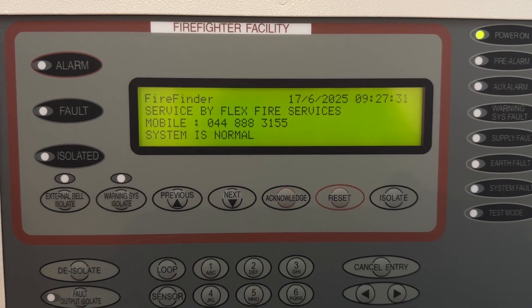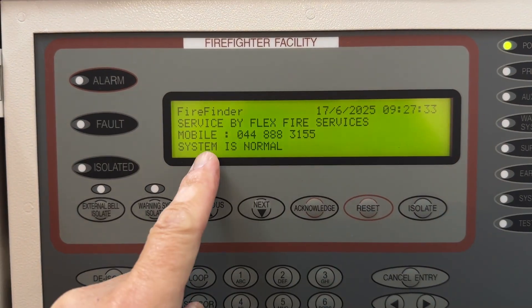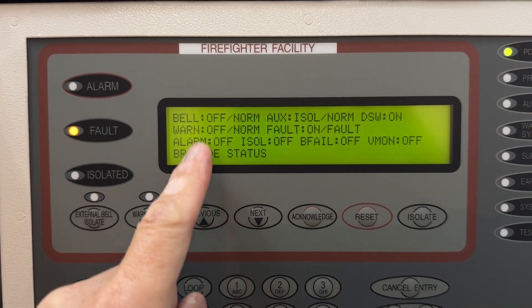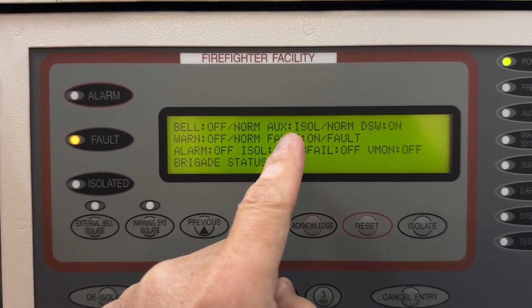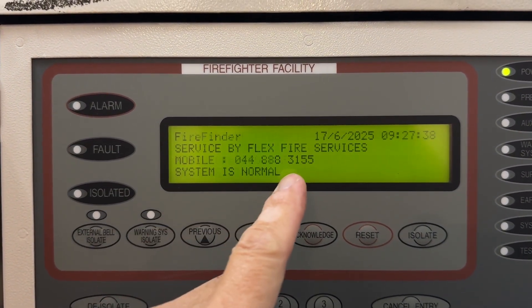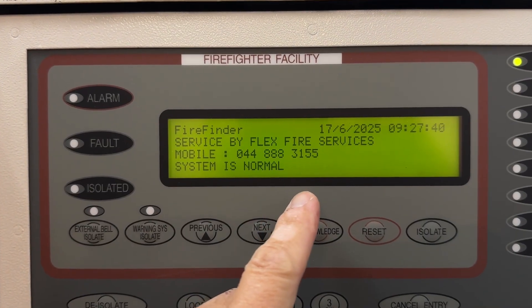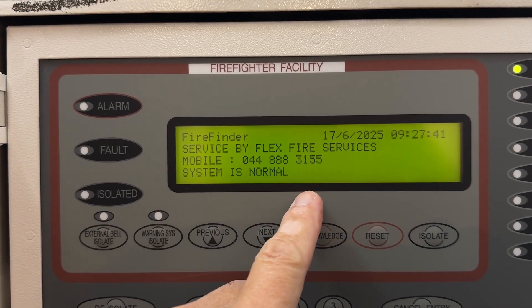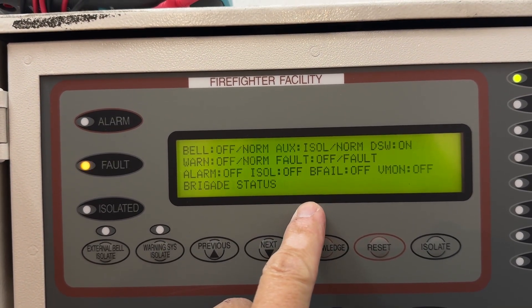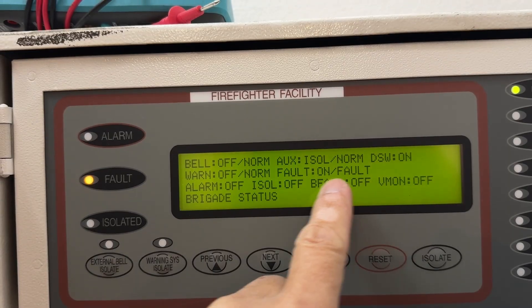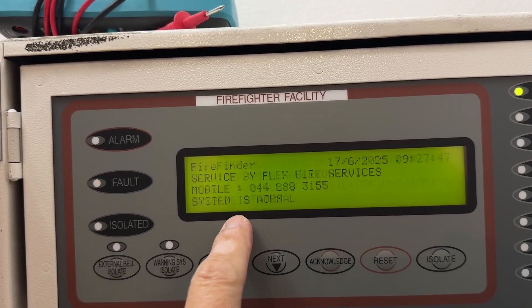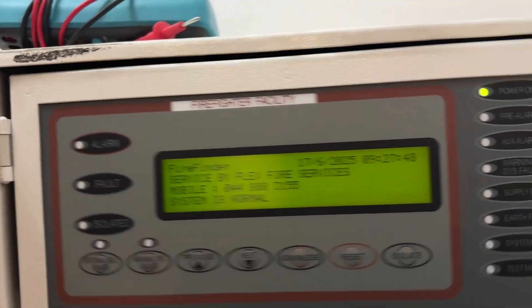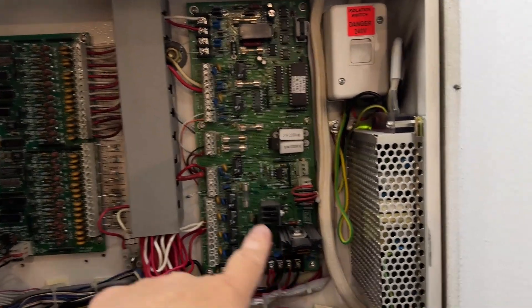So this is your normal status. Let's see. Bell is okay, auxiliary okay, that's okay. And one thing you see is the fault relay is the one that's clicking on and off. There's a fault there on the brigade card. Brigade card is that.